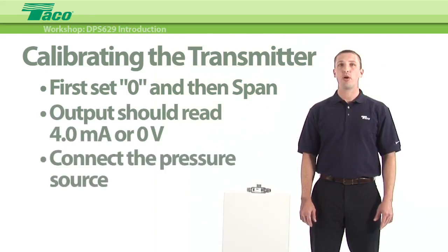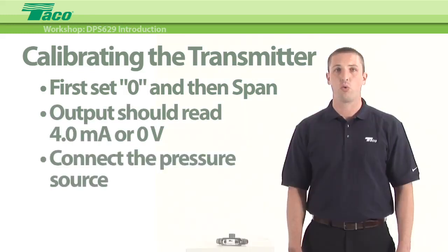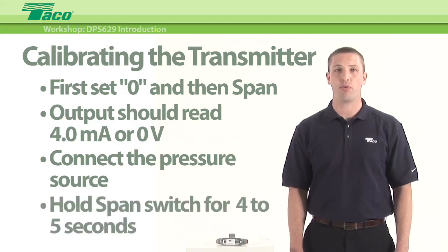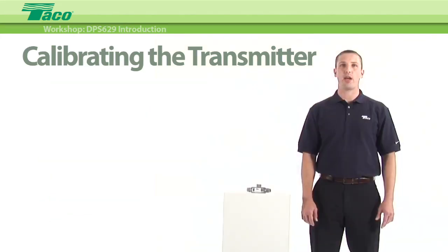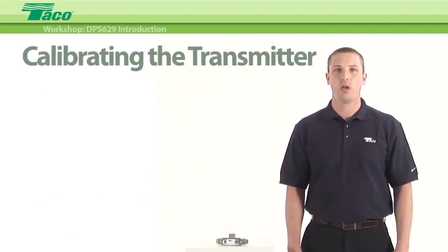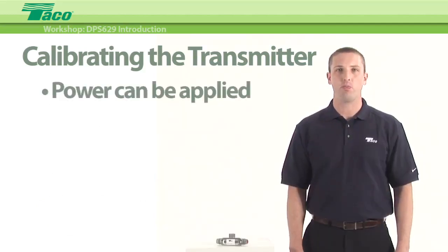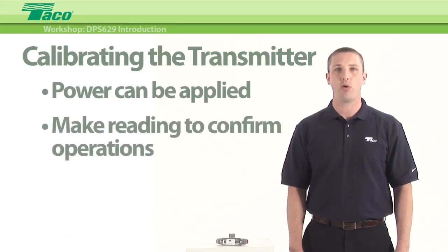Now, connect the pressure source and apply the high range rated pressure. When the pressure is stabilized, press and hold the span switch for about 4 to 5 seconds. The display, if present, will now read the calibration pressure. Provided that calibration is satisfactory, the setup process should now be complete. Power may now be applied to the system, and once at steady state, you may wish to make a few readings to confirm operation.